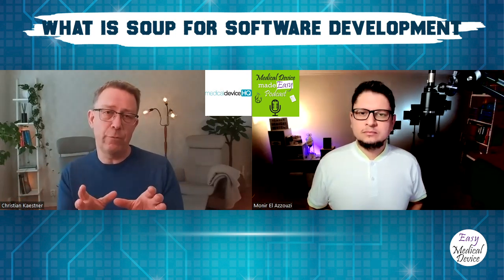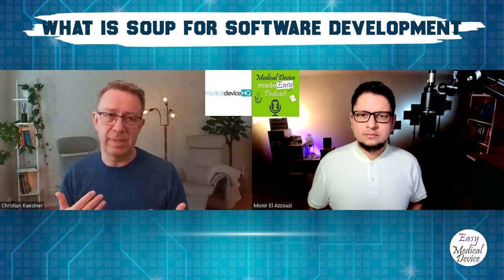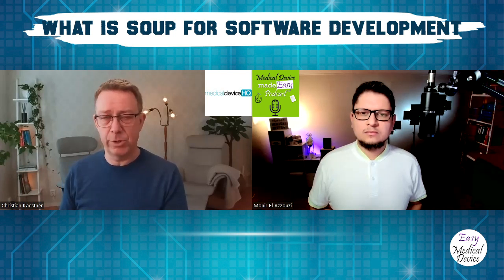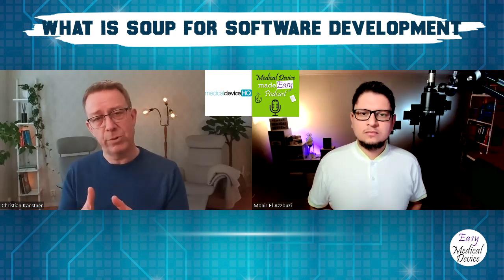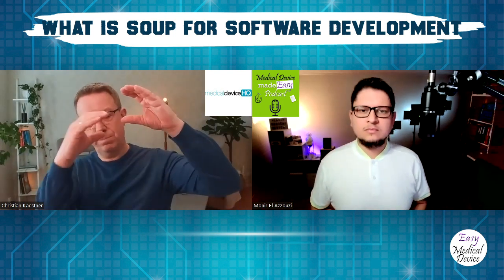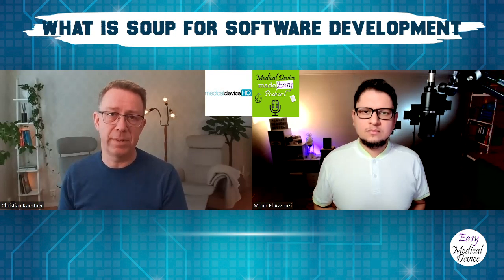And 82304-1 is the counterpart on the product standard level. So it defines high-level requirements about how to develop standalone software, SaMD, and then for the development part it points to 62304. So you can say 82304 is on top, and then below that it references 62304 for the development part.